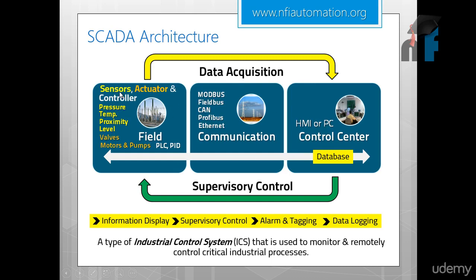Typical sensors include pressure sensors, temperature sensors, proximity sensors, and level sensors. Actuators can be valves, motors, or pumps. Controllers include PLCs and PIDs — PIDs typically for dedicated temperature control, PLCs for step and analog control. Communication protocols include Modbus, Fieldbus, Profibus, and Ethernet, by which field devices interact with the control center. The control center uses HMIs or PCs to control field devices via the communication network and acquire data.